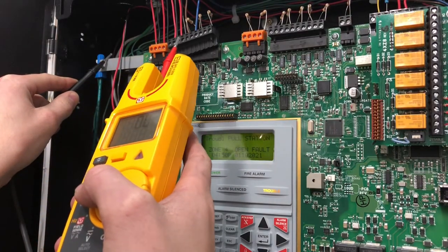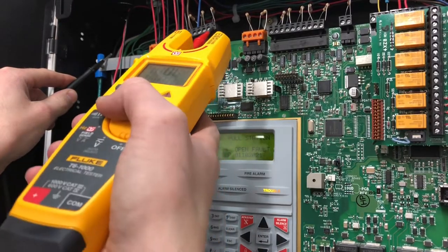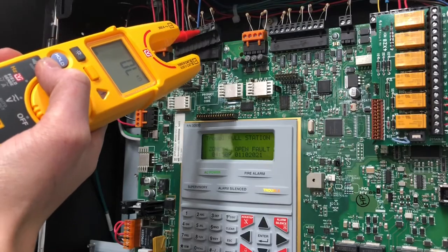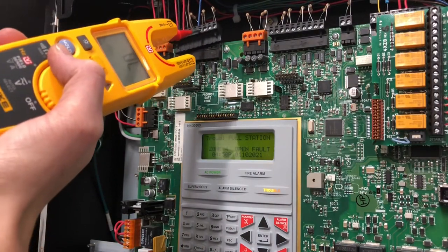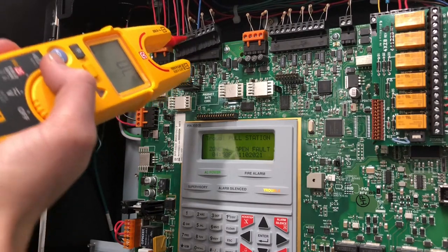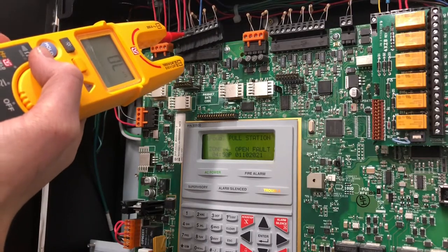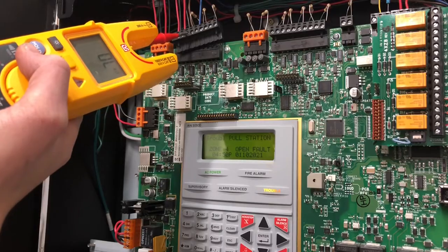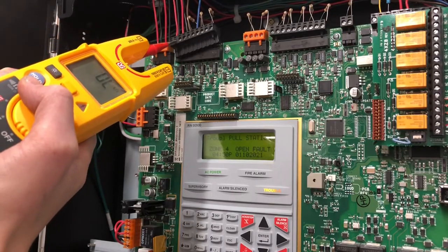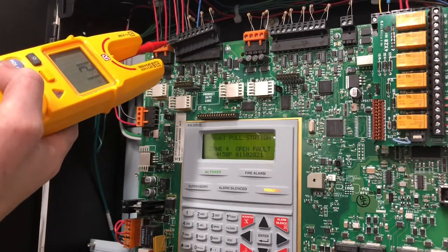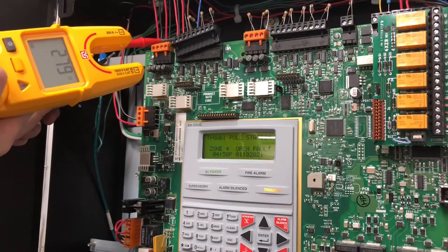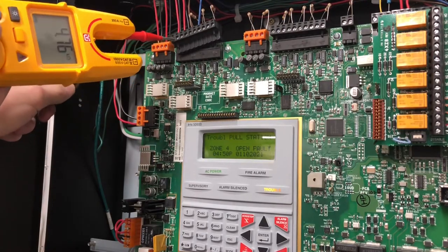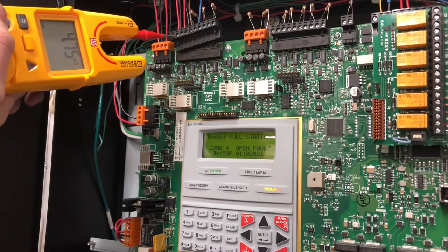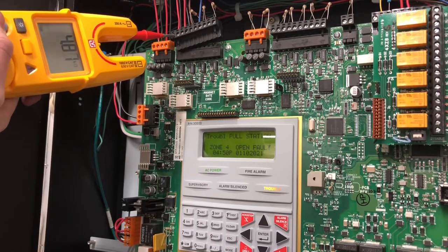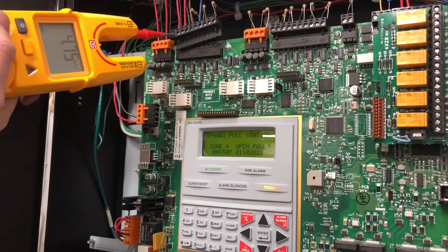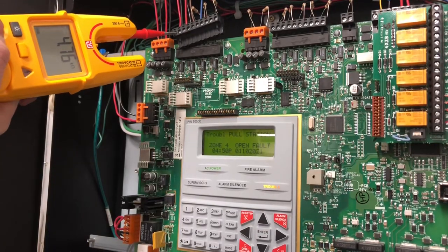So now we're gonna test each zone. And I know this is zone 1, so I'm gonna go from the other way. So we have OL, OL, OL, OL, which stands for, I believe, open line or overload, meaning there's infinite resistance. There we go. So we found our ground fault. So if I go to the positive, we have 4.76. So basically just from that, we know that it's after the end of line resistor, that basically the positive travels through, goes through your last device through the end of line resistor, and then comes back and is going to ground at some point after that end of line resistor.